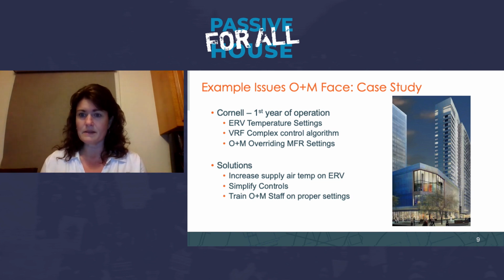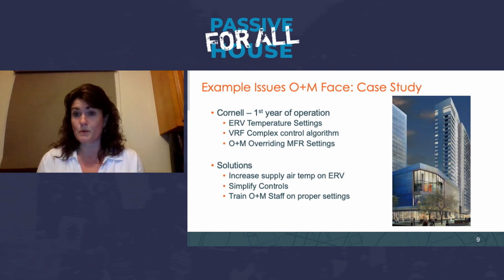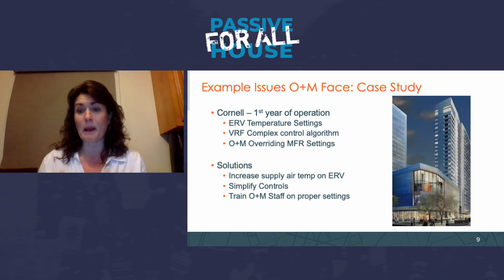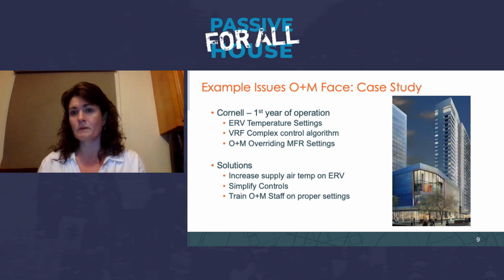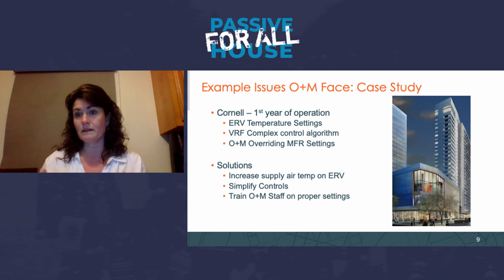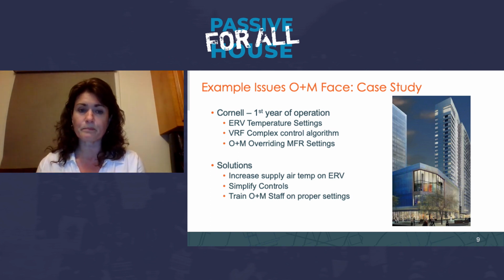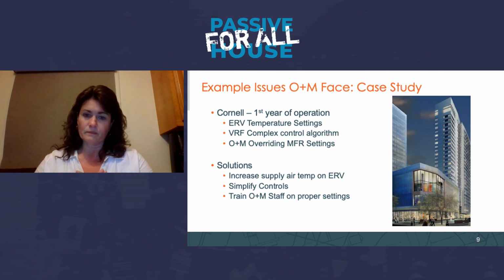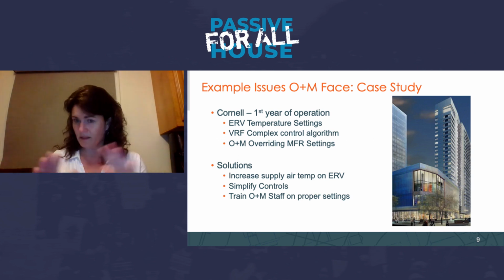And because the O&M staff didn't understand what was happening, they were getting so many comfort complaints because it was towards winter and people's systems were switching over into cooling mode. And so there were some very unhappy occupants the first year. So the O&M staff started overriding some of the settings in the indoor apartment units. So we got it all straightened out in the first season.